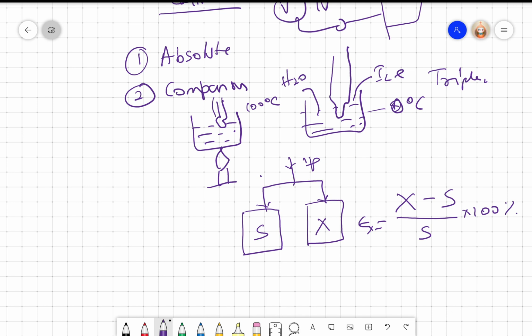So this is quite popular. Here what we are doing is we are finding out the error in X by comparing it with a standard. Now, what does standard mean? Standard must have error much less than X. Standard is supposed to be error free, but we all know it's impossible to make a measurement without errors. So the only thing is, if you are calibrating a 1% accuracy transducer, then your standard has to be at least 0.1% accuracy or 0.05% accuracy, so that this is sort of valid, right?